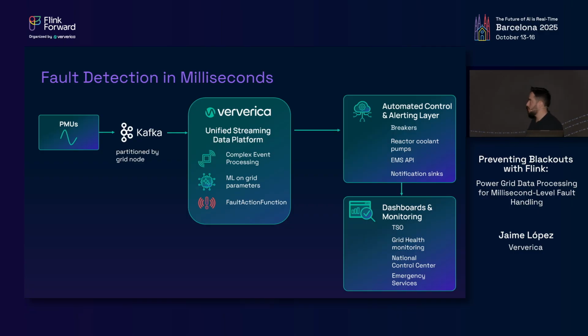What is that analysis? You can do complex event processing, either set some basic rules for what might happen, for voltage sags, for angle jumps, and you can adjust those rules on the fly when the situation needs it. What you might need in the morning peak is different than the evening peak. What you might need in the winter might be very different than in the summer, because renewable generation is going to be very different. So with complex event processing, you can have a really good grip on how these events look and whether or not a fault is happening.